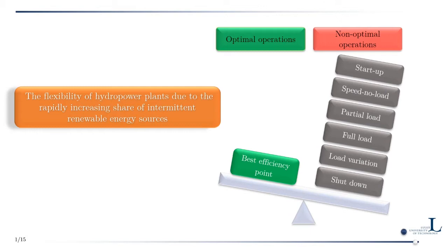Hydraulic turbines are designed to operate at a certain operating point for a specific head and discharge, known as the best efficiency point. However, due to grid demands, off-design operation — ranging from startup, speed no-load, part load, full load, different load variations, stops, and runaway conditions — has increased. There is therefore an obvious need to predict load fluctuations during off-design conditions, particularly on runner blades, to prevent harmful operating points and predict the refurbishment period of turbine runner blades.